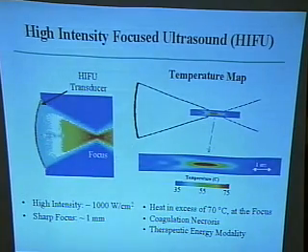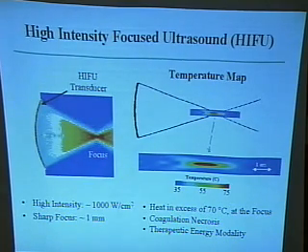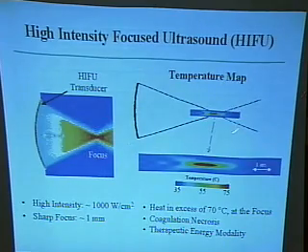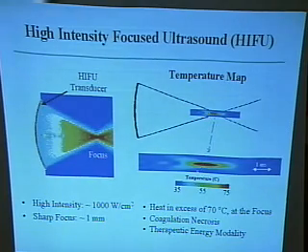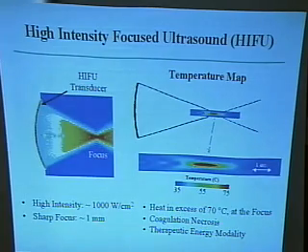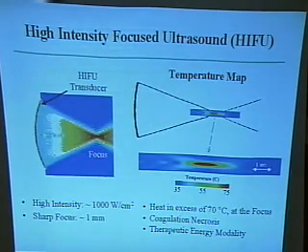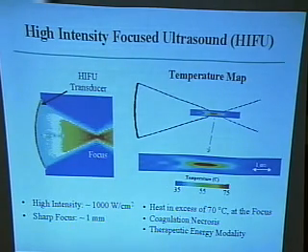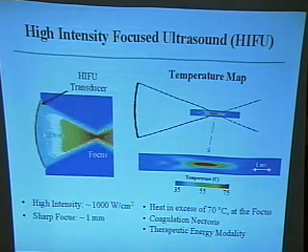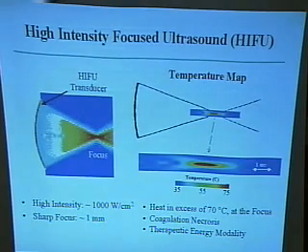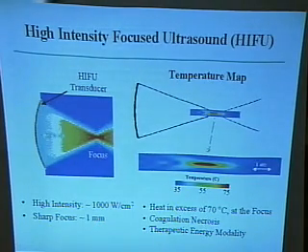What you could do with this concentrated energy in the tissue is raise the tissue temperature. This is the thermal effect of HIFU. So in this simulation, we are showing that the tissue temperature after about 1 second gets to about 70 degrees in this region, the focal region of HIFU. This has actually been known for quite a while in hyperthermia. In 1 second at 70 degrees C, you cause coagulative necrosis. So that's what it is. And by doing this, you get your therapeutic energy modality.